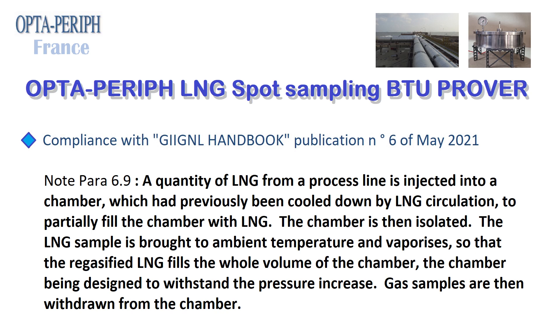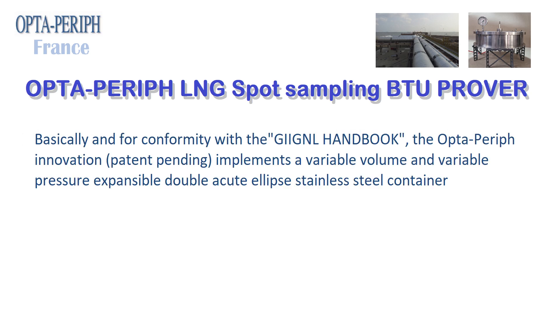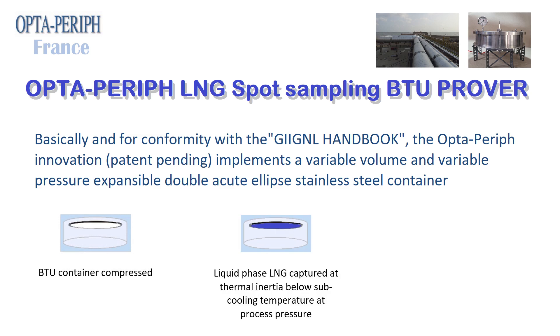The LNG sample is brought to ambient temperature and vaporizes so that the regasified LNG fills the whole volume of the chamber, the chamber being designed to withstand the pressure increase. Gas samples are then withdrawn from the chamber. For conformity with the GIIGNL Handbook, the Opta-Periph Innovation Patent Pending implements a variable volume and variable pressure expansible double acute ellipse stainless steel container.